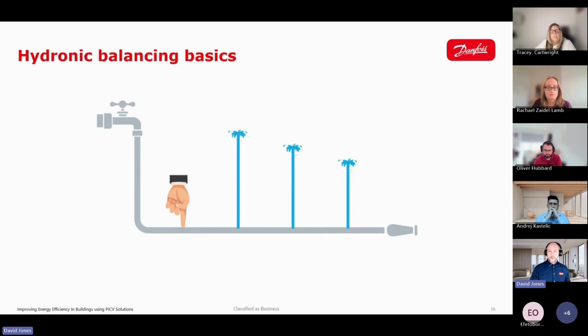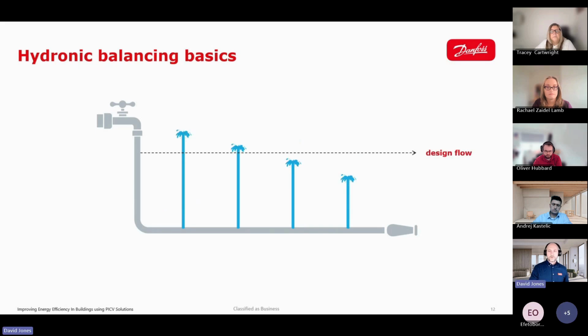If we close off the first hole, or close a demand to a heat emitter, the available pressure in the 3 remaining holes increases further down the hose. So we are now receiving a higher flow of water. If we close off 2 holes, again, we get an increase of flow in the 2 remaining holes. The water flowing through the hose isn't at the design flow that the system was designed to work and be efficient at.